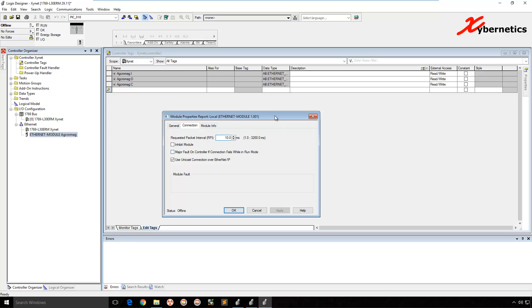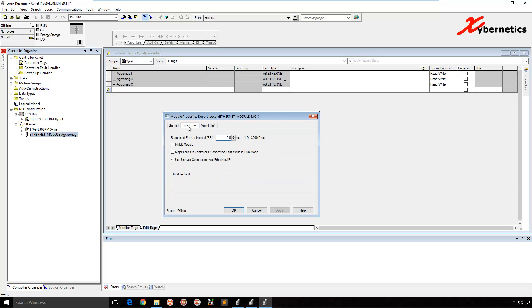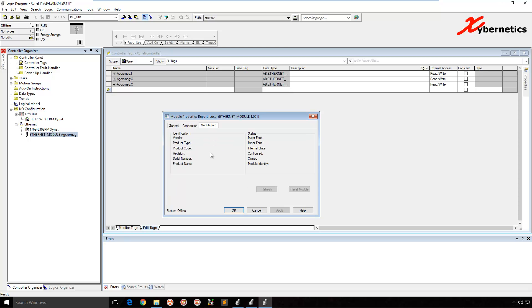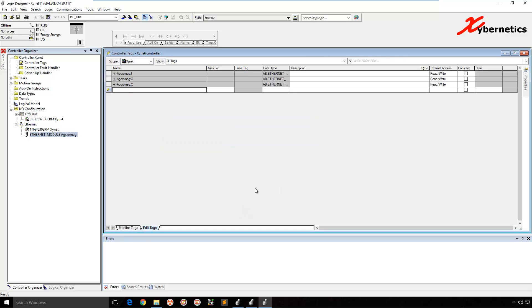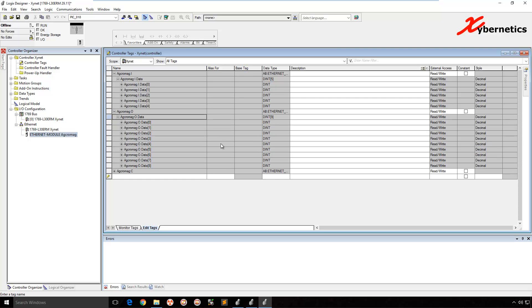I just want to touch base a bit here. This is where you started from. Connection. If you are dropping, if your comms are dropping, increase this by another 10 milliseconds, or maybe another 20 milliseconds. This will help with your comms. And the modules is everything about the modules. But we're not live, so it's not showing here.